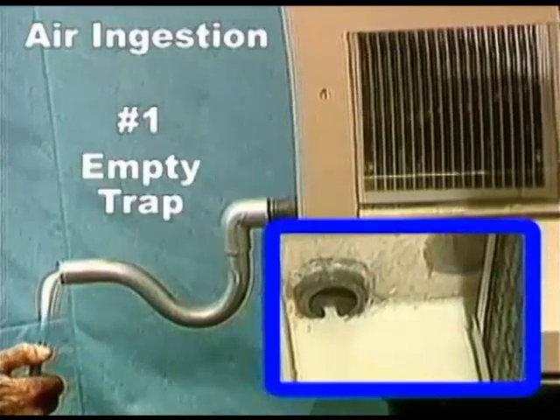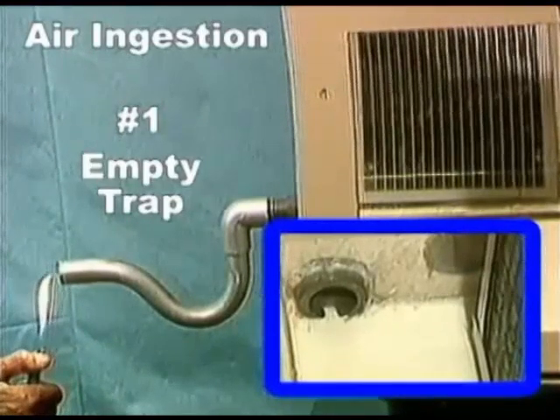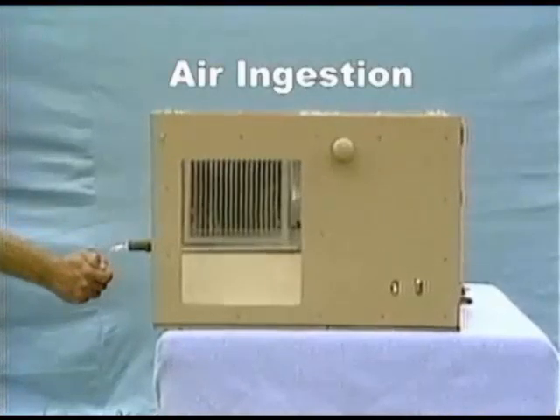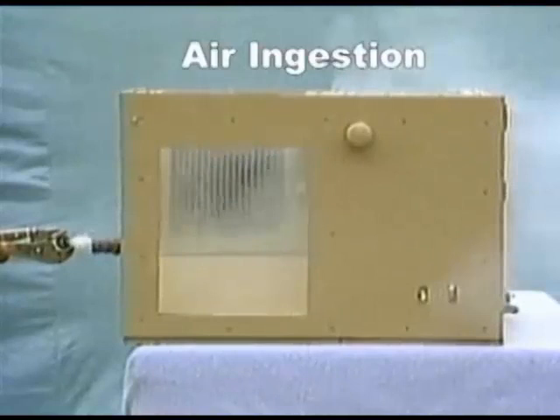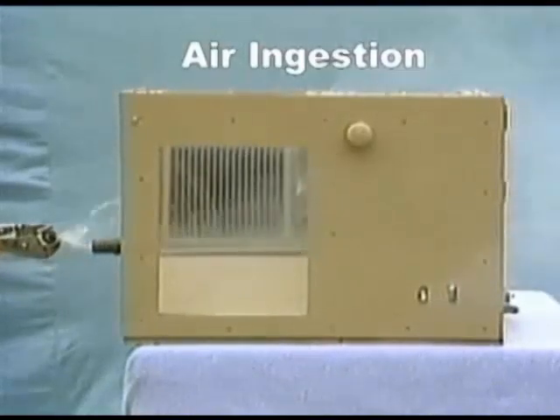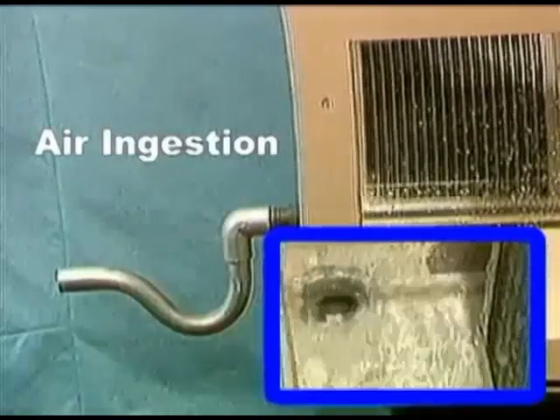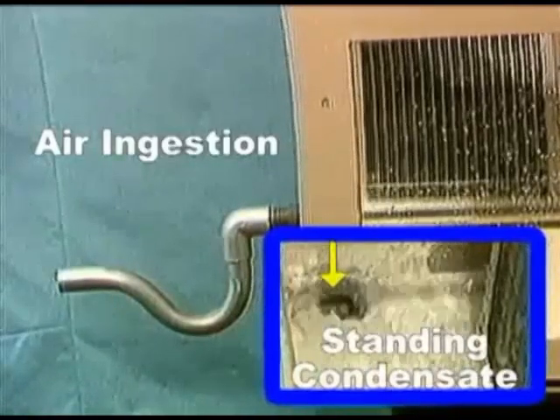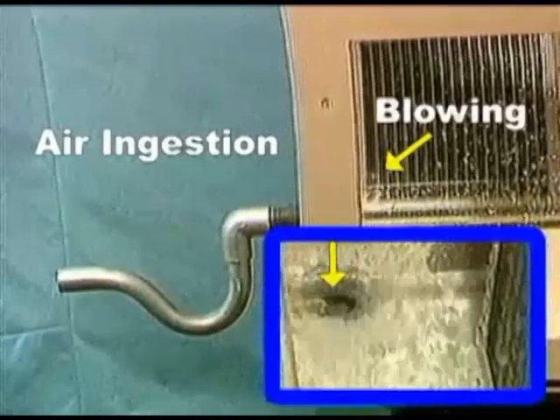During startup for summer cooling and during winter operation, the empty trap has no seal and acts like a missing trap, allowing air ingestion. If present, toxic or noxious air near the drain outlet will be spread into the building. This ingestion of air also causes condensate to stand in the pan and leads to condensate blowing inside the air conditioner.